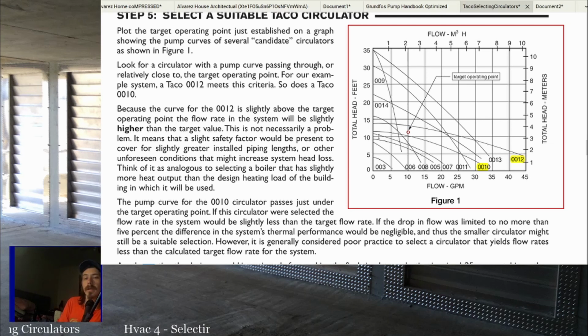So we can see the 0010 right here. We can see the 0012 right here. All the other ones are a bit farther away. This 009's kind of close, but not really. And the 008 is kind of close, but not really. So because the curve for the 0012 is slightly above the target, the system flow rate will be a little bit higher than your target value. So you're going to have slightly more flow if you put in a 0012 than you calculated for, but slightly more is generally better than slightly less, right?